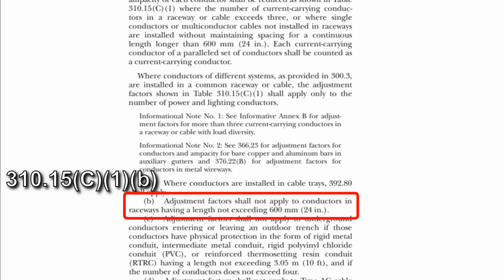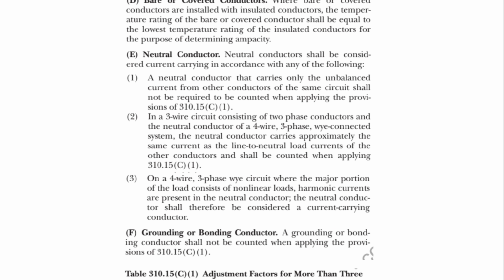Another interesting detail is that adjustment factors shall not apply to conductors in raceways having a length not exceeding 24 inches. So if the conduit is 24 inches or less, we don't bother adjusting the ampacity of 3 or more current carrying conductors. So how do we handle neutrals and ground conductors? It's pretty simple in this case.